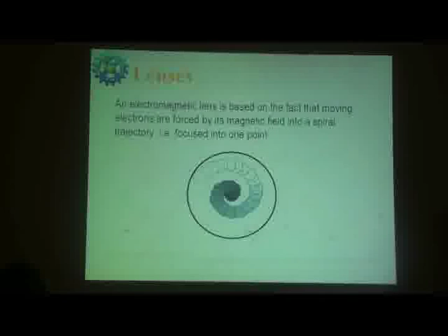If you increase the lens current more and more, that is inversely proportional to the focal length, so you are exciting the coil very high, strengthening the lens. That means the focal point will be reduced. These are fixed except the lens current, with which you excite the lens. If you increase the current, you are reducing the focal length of the lens.